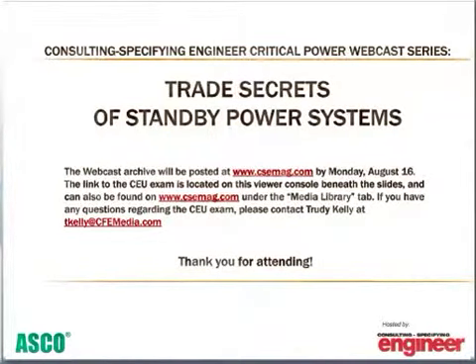Great. And Jason Harrell is asking you from Integra Telecom, should a neutral grounding resistor be used in a system with generator backup to help with reducing faults? So that's a similar type question. Basically you size a neutral ground resistor. With a solidly grounded system, which is 99% of what you see, when you have a fault it produces enough current to trip the breaker. With a high impedance ground, you size it so that you will only have, say, 5 or 6 amps running through your fault, which will not be large enough to trip your breaker, but will be high enough to trip an alarm. Just a little more complex for design, but yeah, we see those in higher end data centers with high voltage generator systems.